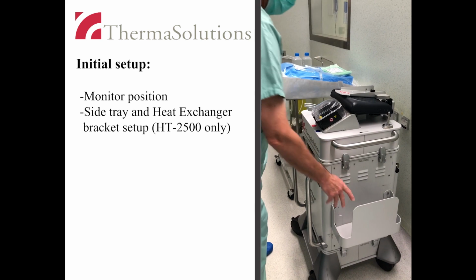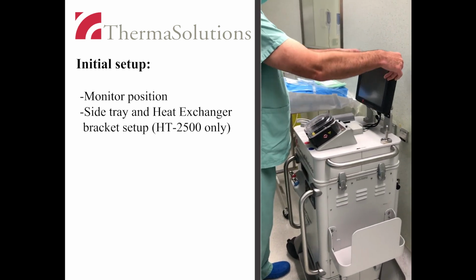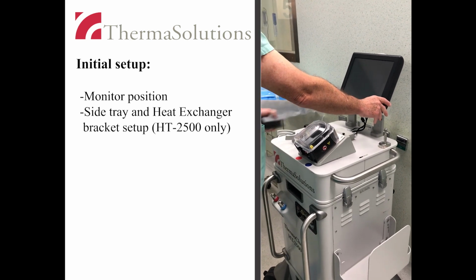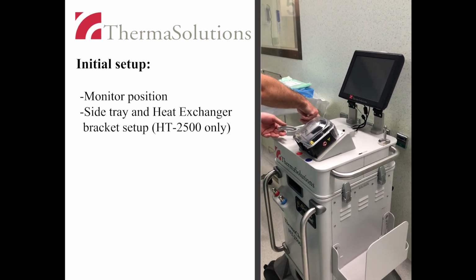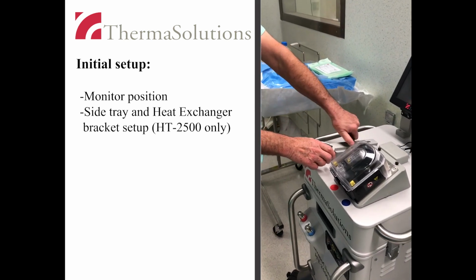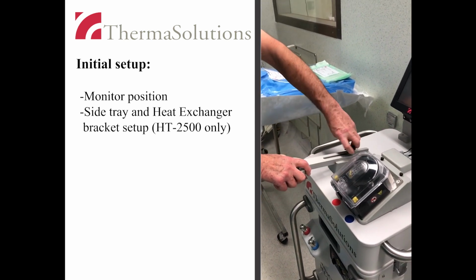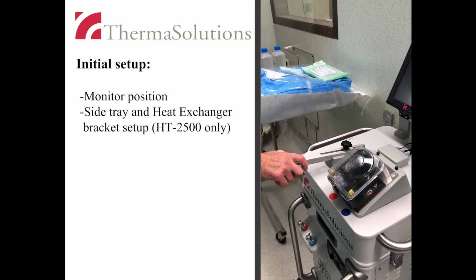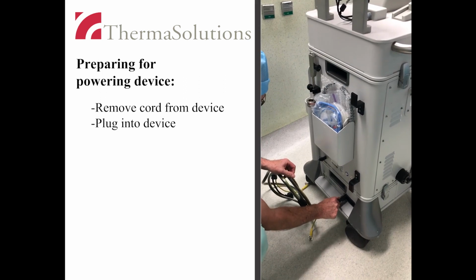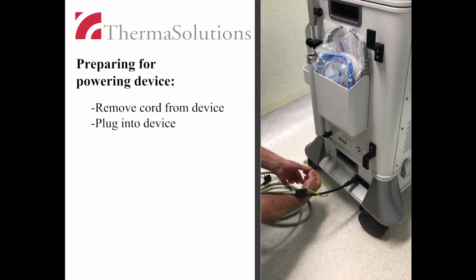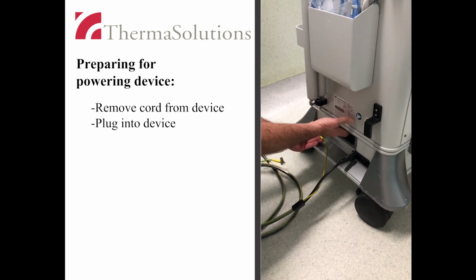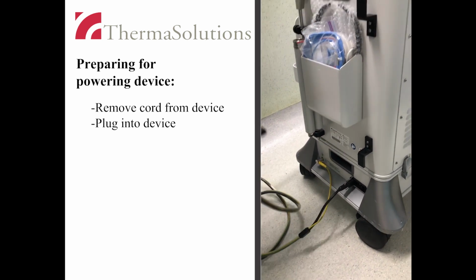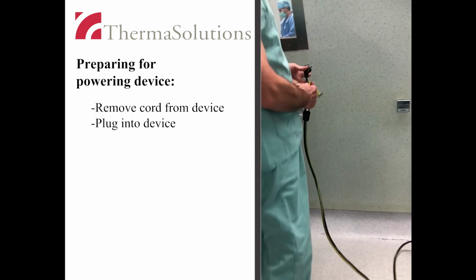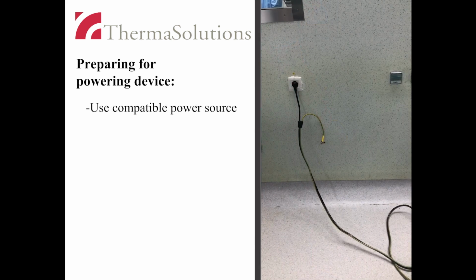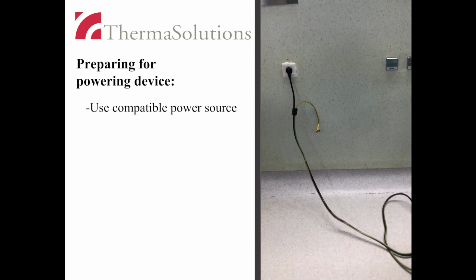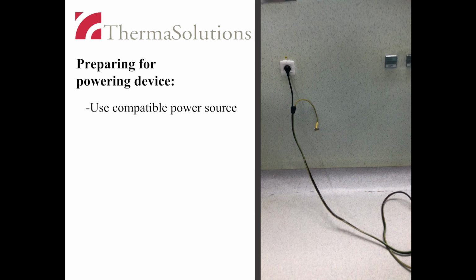Initial pre-setup may include positioning of the monitor, the side tray, and the heat exchanger bracket. The IV hanger rod can also be attached at this point. Make sure the power cord is fully inserted into the socket in the back and also into the wall receptacle. The power cord and adapter should be appropriate for the power receptacles. Local power requirements are considered prior to the shipment to the ThermoChem unit.